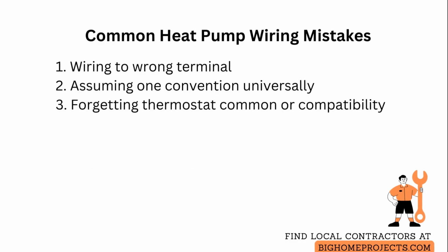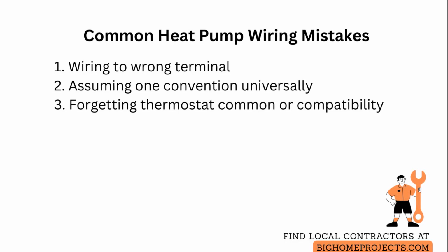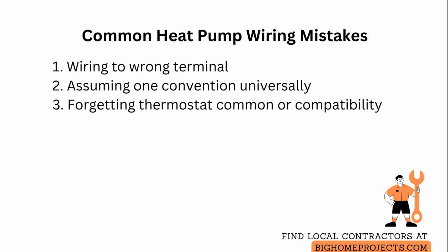The three common mistakes are wiring the reversing valve to the wrong terminal, expecting one convention to apply to every brand, and assuming the valve coil does not require a common. Wiring to the wrong terminal makes the system run in the opposite mode, so swap the conductor to the correct terminal and test in both heat and cool.